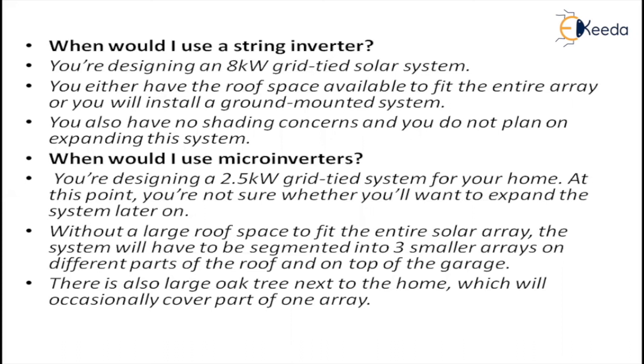Microinverters are used from a 2.5 kilowatt grid-tie system for your home — for instance, when you are not sure whether you want to expand the system later on, without large roof space to fit an entire solar array, with the array segmented into 3 solar sections on different parts of the roof, or where there is a large tree nearby that will occasionally shade part of one array. Wherever there are shading effects and such issues, and you want to expand your system, you can install a microinverter-based PV panel system. But where there is no expansion needed and no shading effects, you can use string inverter systems.